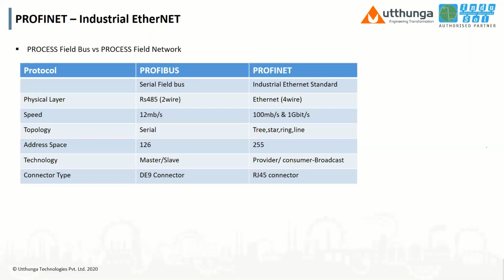While PROFINET can have tree, star, ring, line, any topology. And the number of slaves in PROFINET is 255. Not slaves, we cannot mention slaves in PROFINET. In PROFINET we call them controller and IO devices, while in Profibus we call master and slave. Technology in Profibus is master slave. Already we discussed, and in PROFINET technology is provider and consumer, that is broadcast. In PROFINET, connector types are RJ45, that is similar to Ethernet standard, but we recommend industrial Ethernet connectors. Why? Because proper grounding has to be taken in the network, otherwise future problems will come out. And in Profibus, sub-D9 connector. These are the basic differences between Profibus and PROFINET.